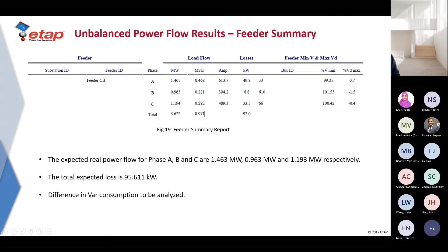That can be attributed to the fact that the loads are modeled, especially the single phase constant current loads, slightly differently than what's expected. One of the things about the data sheet in the IEEE 123 system is that all the loads are marked as spot loads. So it is very difficult to analyze what time of the day these loads will attain their peak, or how their loading is distributed over summer or winter. When you take diversity factors into account, it is important to analyze the loading scenarios for summer, winter, day, night separately.